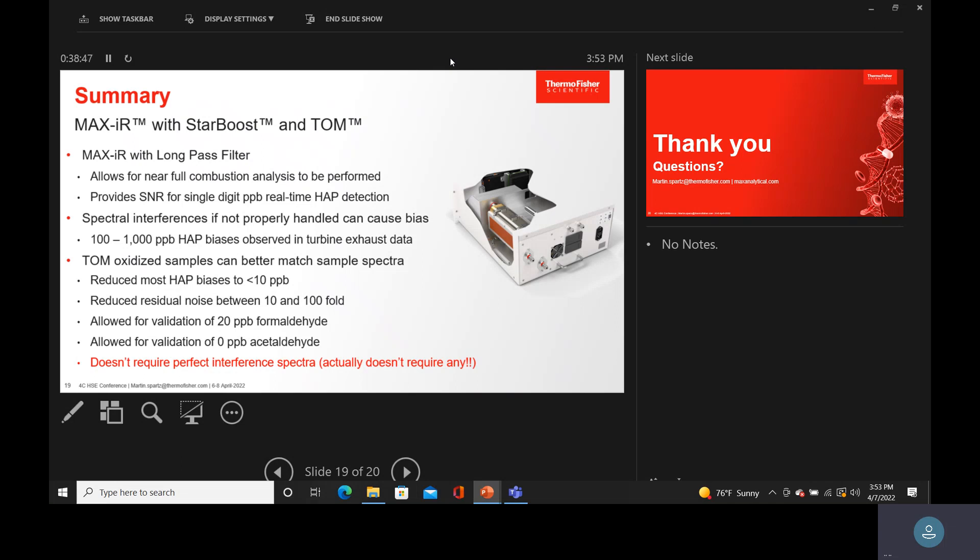For these types of applications we set up the whole recipe. If they have the TOM and our sampling system, we can automate the entire thing — it'll collect all the calibration data, all the system data, all the spike recovery data, and the spike recovery data while going through the TOM, all automatically. Each file, depending on what step it is, has a name and we can tell it to use it or not.